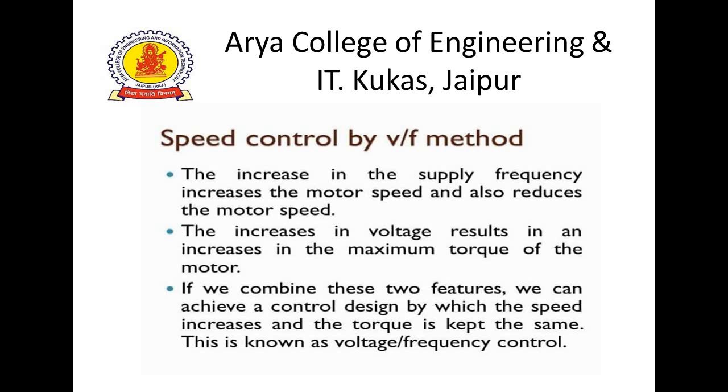Next method is speed control by voltage and frequency method. An increase in the supply frequency increases the motor speed, and a decrease reduces the motor speed. An increase in voltage results in an increase in maximum torque of the motor. If we combine these two features, we can achieve a controlled design by which the speed increases and the torque is kept the same. This is known as the voltage and frequency control method.